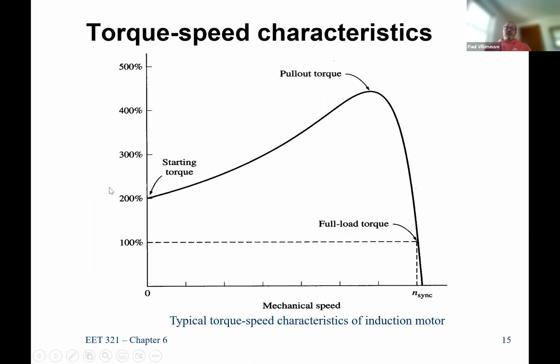Well, that's pretty good if you look at this curve, and we can vary this curve characteristic or its curve shape. But for a typical, and we'll learn more about the NEMA design, but for a typical induction machine, we have a starting torque of about 2 times greater than its full load torque, which is important because, again, we're hitting this at no speed. This is our locked rotor condition. This is when the thing is pulling in a lot of current. It's not really putting out any torque, right? Because if power equals torque times omega, if it's at 0, then obviously it can't do anything. But over here, this is just after we leave 0. But it's able to put out 200% of its nominal value.